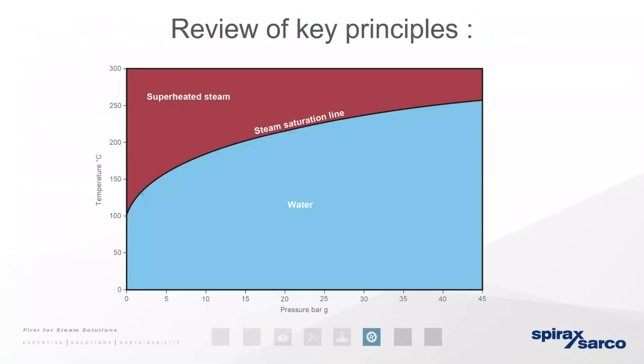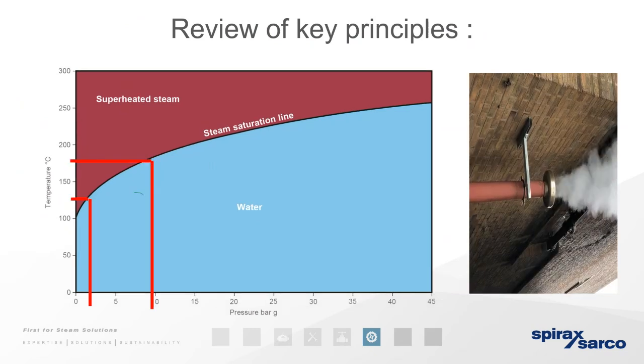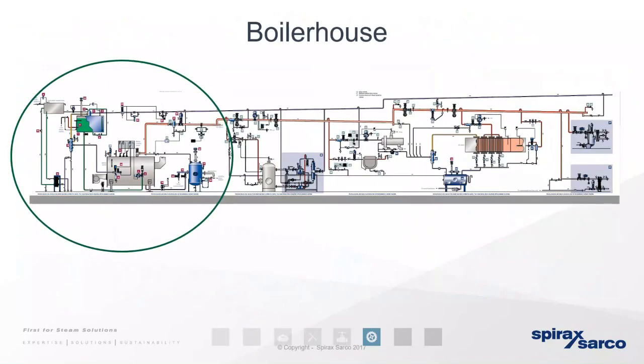So superheated steam: everything on that line, as you can see, is steam. It means it can effectively be condensate at that temperature around steam. Below that line is going to be water, and above that it means you've added more energy to it, so it's become superheated, so it's become drier. In this particular case, you can see that at 10 bar, we have a temperature of roughly about 184 degrees for steam. And at 2 bar, it's about 130 odd, I think. So boiler house, again, it's part of the larger system, so you may have many, many things upstream. In this particular course, we're talking about the boiler house itself.